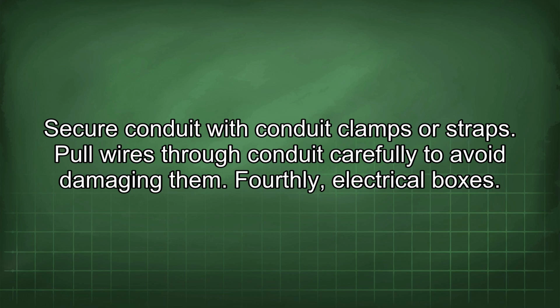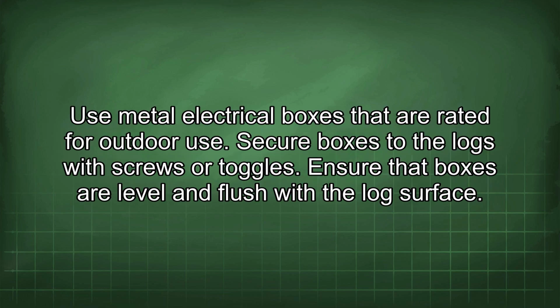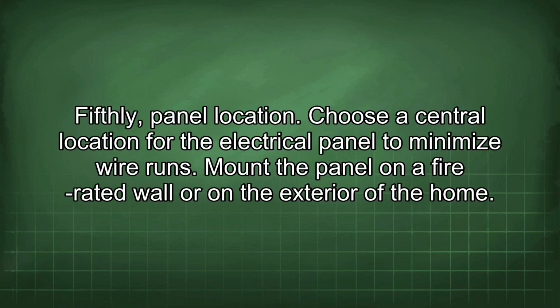Fourthly, electrical boxes. Use metal electrical boxes that are rated for outdoor use. Secure boxes to the logs with screws or toggles. Ensure that boxes are level and flush with the log surface. Fifthly, panel location. Choose a central location for the electrical panel to minimize wire runs. Mount the panel on a fire-rated wall or on the exterior of the home.